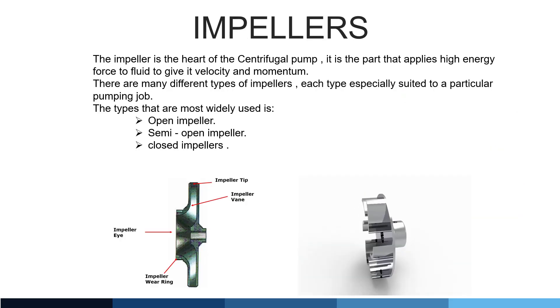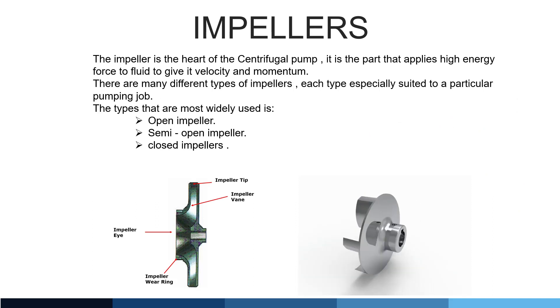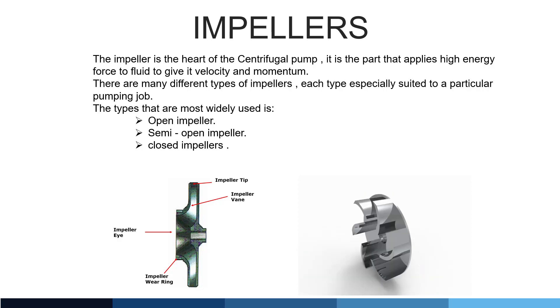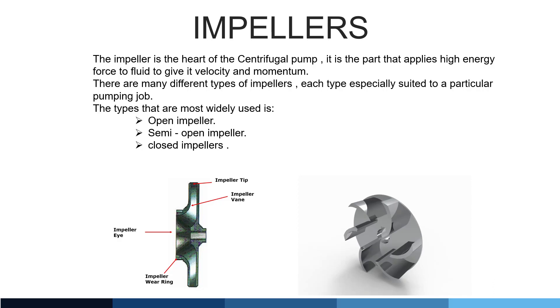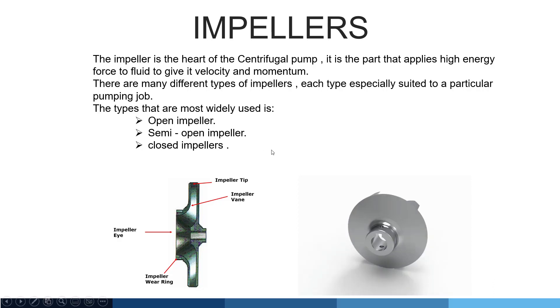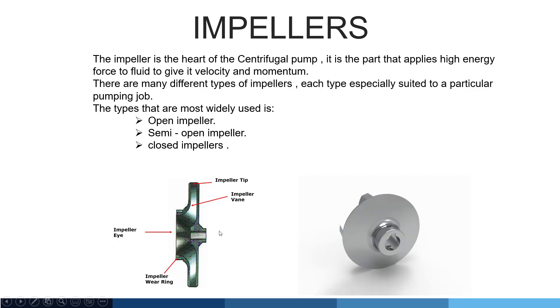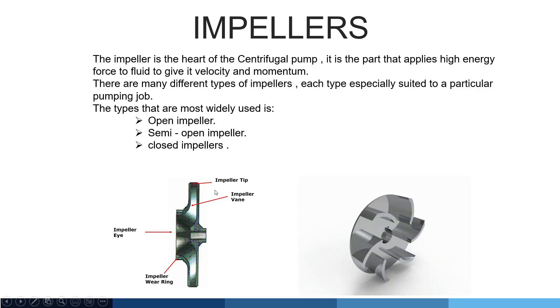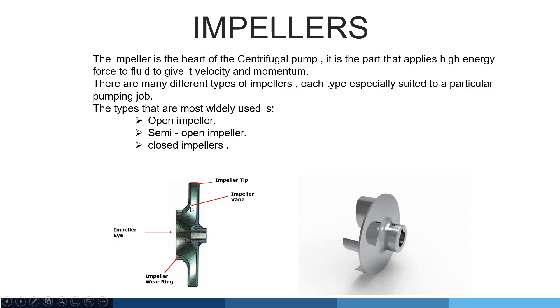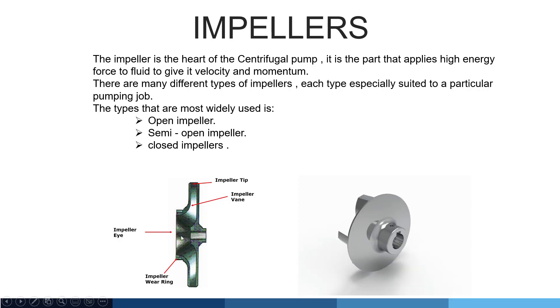The impeller is the heart of the centrifugal pump. It is the part that applies high energy force to fluid to give it velocity and momentum. There are many different types of impeller, each especially suited to a particular pumping job. The types most widely used are the open impeller, semi-open impeller, and closed impeller. You can see the parts of the impeller in this picture: at the top is the impeller tip, this is the impeller vane, the center portion is called the impeller eye, and there are impeller wear rings.